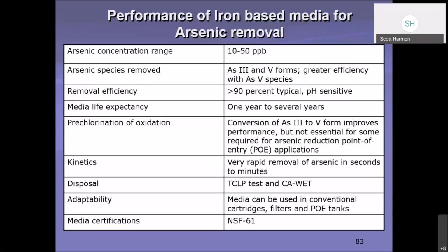Kinetics, very rapid removal of arsenic in seconds to minutes. Disposal, it talks about how you would dispose of it, and there's some guidelines in EPA that'll help you with that. Adaptability, media can be used as conventional cartridges, filters, or point of entry tanks, and anything in water world has to have an NSF approval number. So this one is NSF 61.